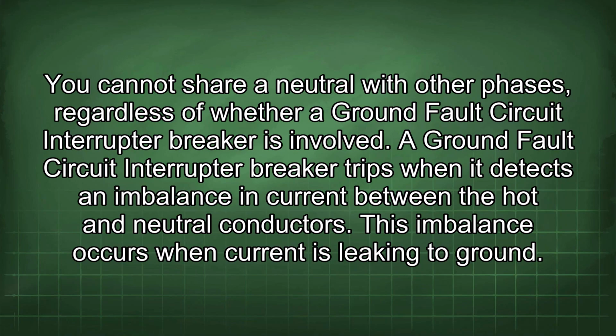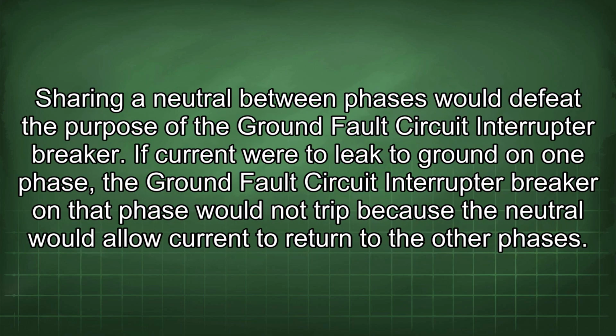You cannot share a neutral with other phases regardless of whether a ground fault circuit interrupter breaker is involved. A ground fault circuit interrupter breaker trips when it detects an imbalance in current between the hot and neutral conductors. This imbalance occurs when current is leaking to ground. Sharing a neutral between phases would defeat the purpose of the ground fault circuit interrupter breaker.